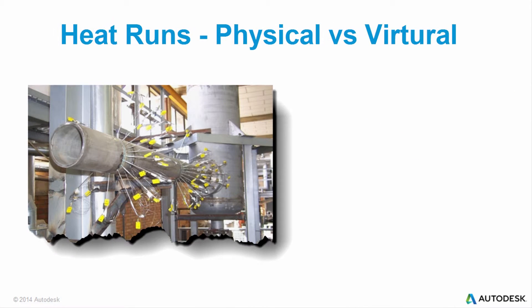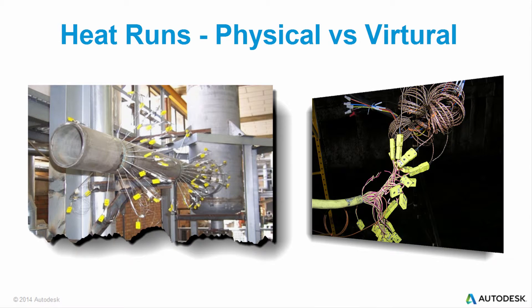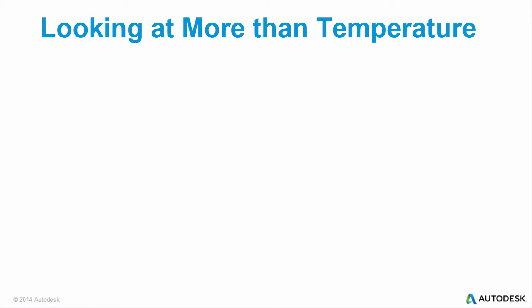Heat runs with thermocouples take a lot of time to set up and only provide results at predetermined data points. Digital prototyping provides visual comparisons and point data without any wires getting in the way. CFD also provides temperature related results that can't be gathered from a physical test.